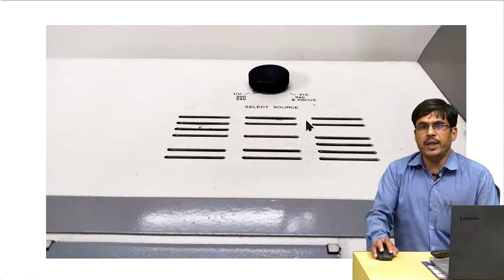This picture shows the sample cell holder chamber. You can see a filter selector here. The filter selector is currently set on filter number 2. What does it mean? You can see a table just below the cover, where the filter number and the associated wavelength in front of it are given.